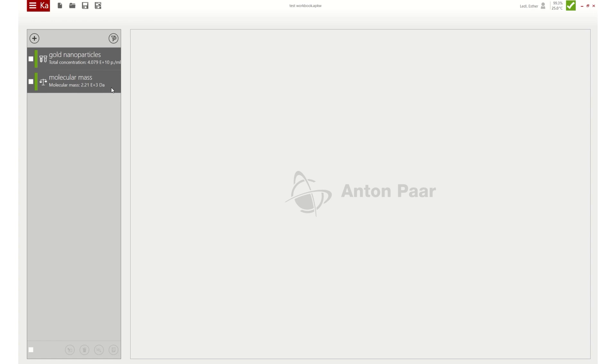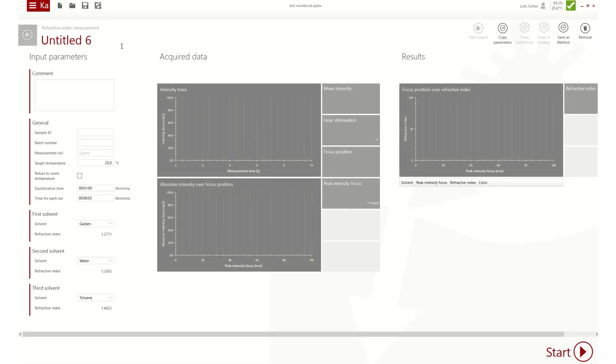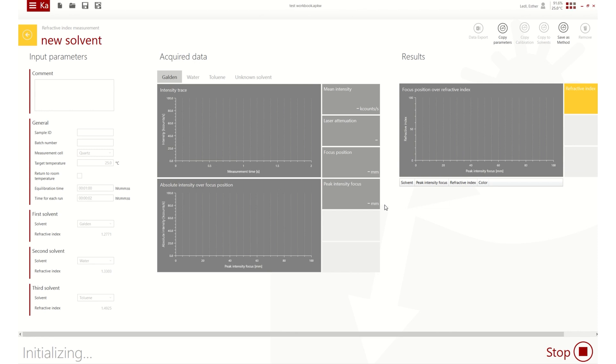The last measurement mode of LightSizer DLS 501 and 701 offers the possibility to measure the refractive index of a sample. This is a mandatory input parameter for other measurement modes. The user is able to accurately determine the refractive index of solvent mixtures, for example, and is able to add custom solvents to Calliope. Measure the sample and three known solvents consecutively. The refractive indices of the reference solvents should represent a wide span of where the refractive index of the sample is to be expected. The refractive index of the sample is calculated from the three solvents.